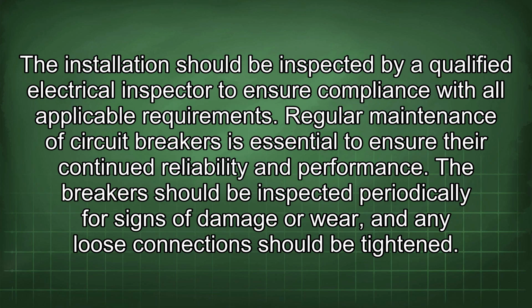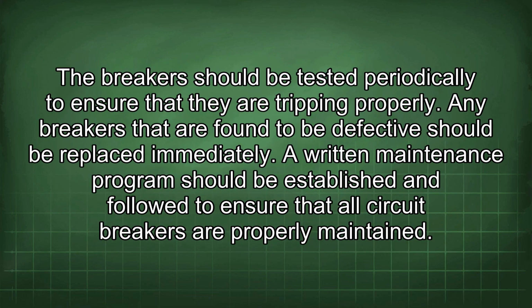Regular maintenance of circuit breakers is essential to ensure their continued reliability and performance. The breakers should be inspected periodically for signs of damage or wear, and any loose connections should be tightened. The breakers should be tested periodically to ensure that they are tripping properly. Any breakers that are found to be defective should be replaced immediately. A written maintenance program should be established and followed to ensure that all circuit breakers are properly maintained.